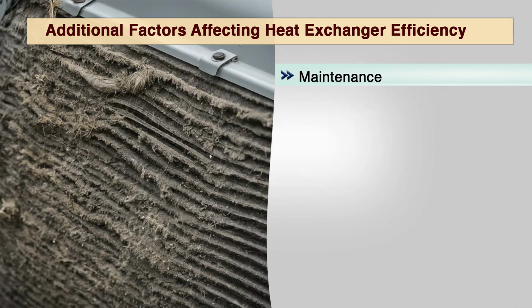of the building. We have covered the key design and material considerations for heat exchangers, but there are other additional factors that can influence how effectively they perform in real world building applications. They are maintenance. Like any mechanical device, regular maintenance is crucial for optimal performance. Heat exchangers can become clogged with dust, dirt or debris over time. This reduces airflow and hinders heat transfer efficiency. Scheduled cleaning and inspections are essential to ensure the heat exchanger operates at peak capacity.